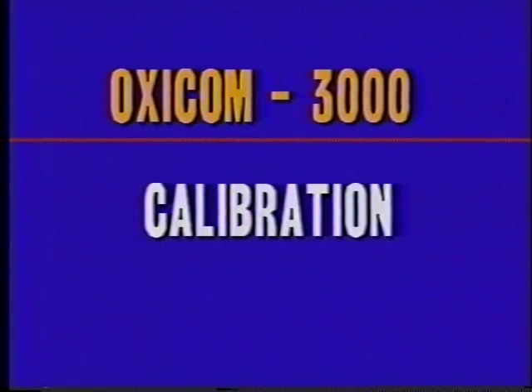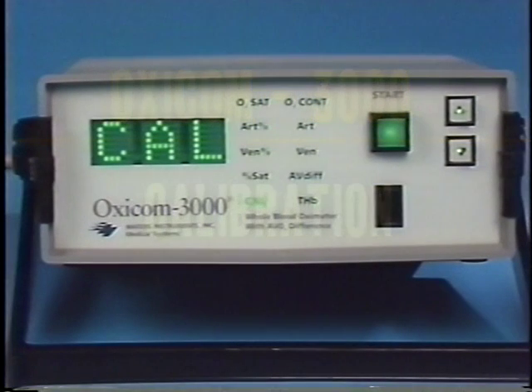Calibration. Proper oximeter calibration is vital to optimum performance. This procedure is mandatory at installation. The daily calibration verification check is recommended for your own records.